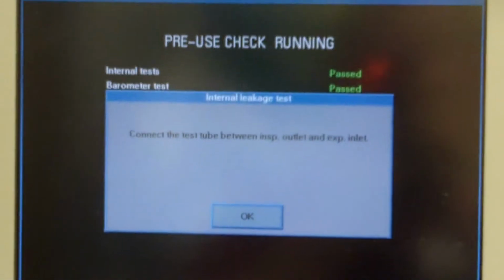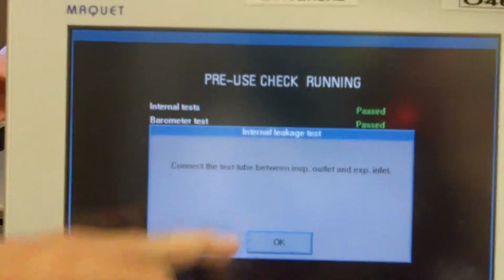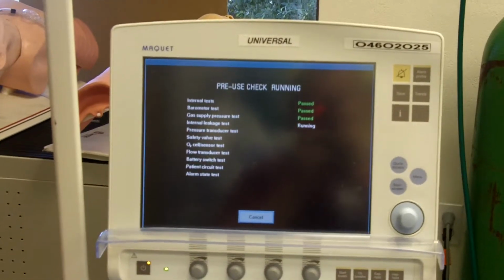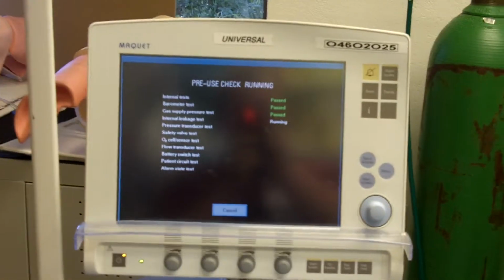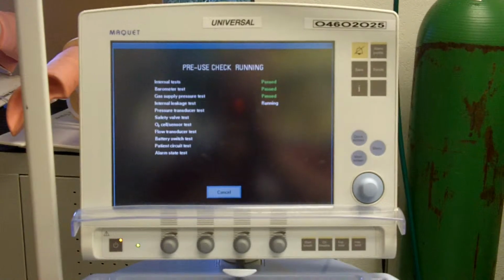Internal test, barometer test, gas supply, pressure test, connect the tube between inspiratory and expiratory outlets where you plug it all in. It's all here on the sides. Inspiratory and expiratory are both marked. And hit OK. Gas pressure, internal leakage, and all that good stuff.